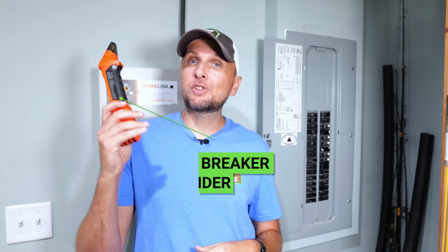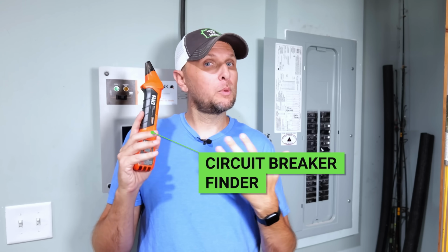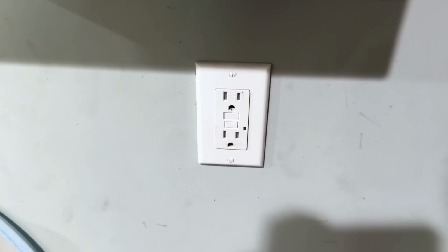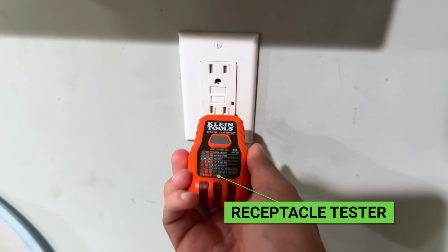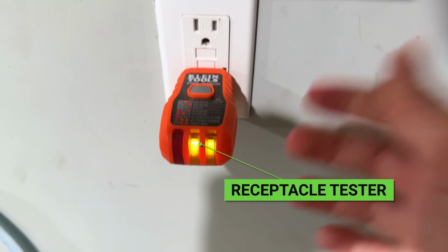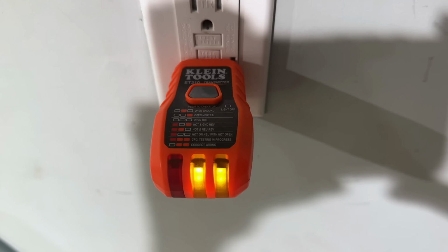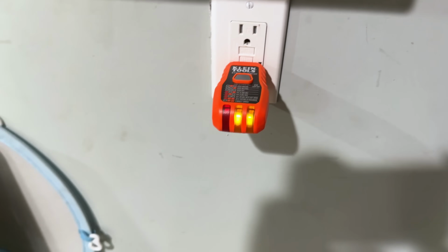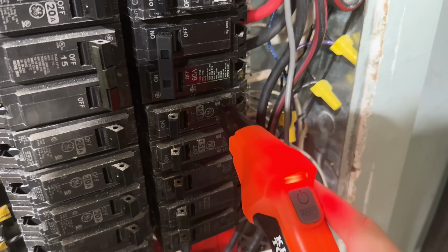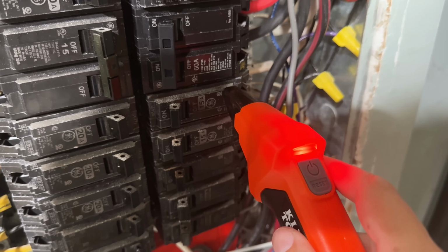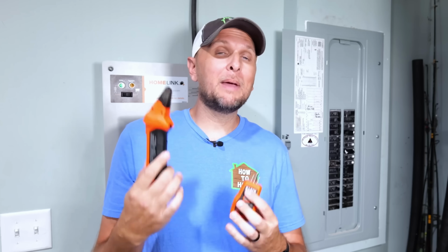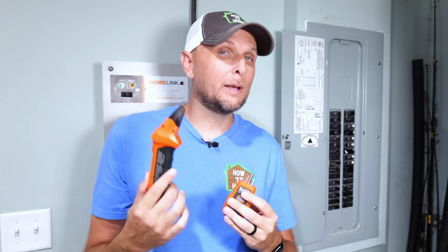But the fixes for this are also pretty easy. You can get a circuit breaker finder like this one made by Klein. All you have to do is take the receptacle tester that comes with it and plug it into the outlet in the room you're wanting to find the circuit breaker for. Then take the gun portion and scan the breakers with it, and it will show you which one is which. I'd definitely recommend having one of these because it can make this job incredibly easy.